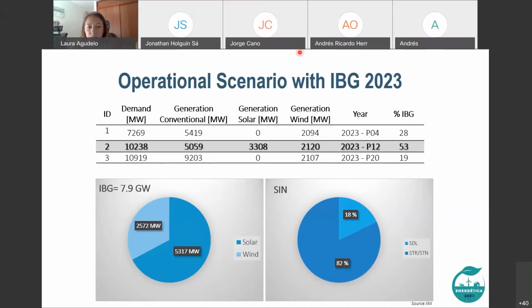And it is important to mention that at minimum and maximum demand it is not possible to have solar generation in this period. In the second line, it is possible. You can see the highest inverter generation because in this scenario solar generation and wind generation are matched. It represents almost 50% of the maximum dispatch in Colombia at this moment. For this reason, this scenario must be included in every protection analysis.